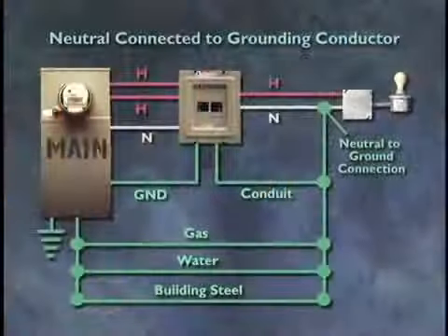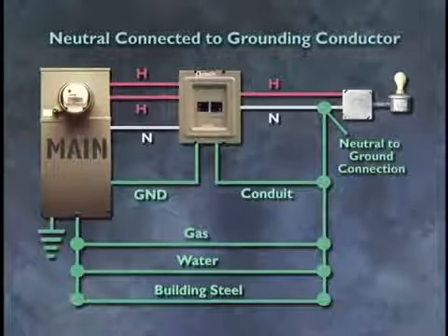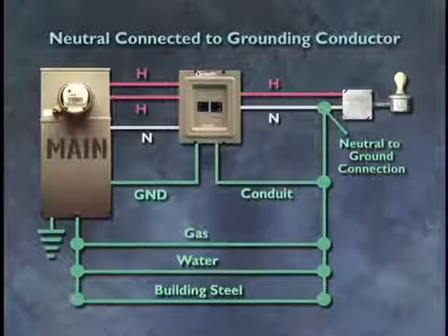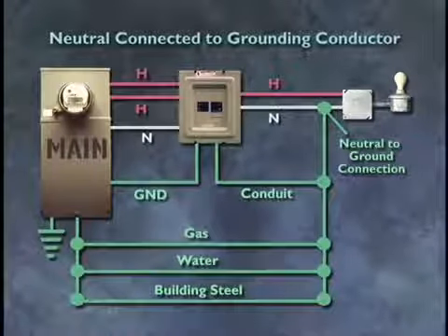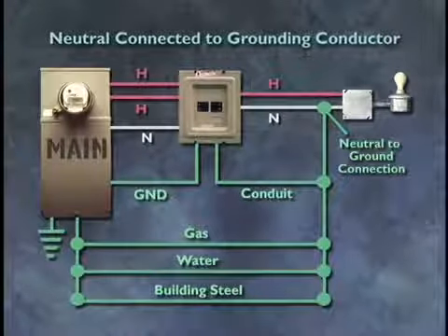NEC 250-24A5 does not allow this connection. There are real dangers involved in connecting neutral to ground within a building. See your written protocol for a fuller explanation. The 1993 NEC Handbook points out the possibility of arcing in concealed spaces leading to fire and the shock potential to workers. When a neutral is connected to the grounding conductors, it will travel in all available metallic pathways which lead back towards the service entrance point.